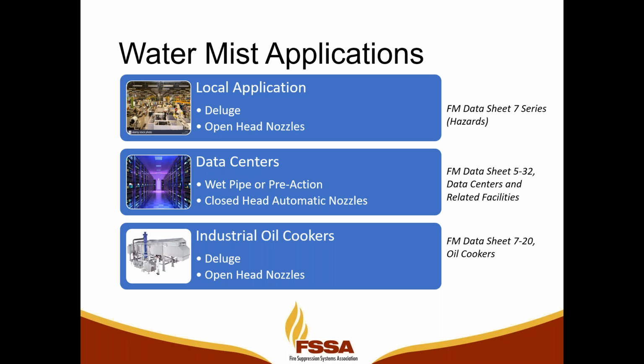Then we've got data centers. There are a few OEMs that have obtained FM's data center approval. So when a given data center is set on using water for its protection scheme, water mist is obviously something they ought to think about if they're concerned at all about collateral damage, because again, with an automatic nozzle, we're going to have half the water output that we would expect to see with a sprinkler system. And we can do either wet pipe or we can do pre-action, where we have a dry pipe where we're holding the water back from the pipe network with a valve.